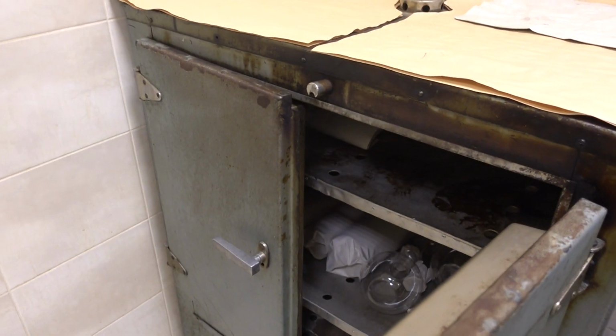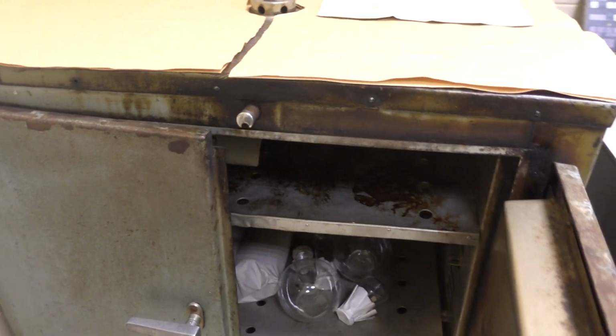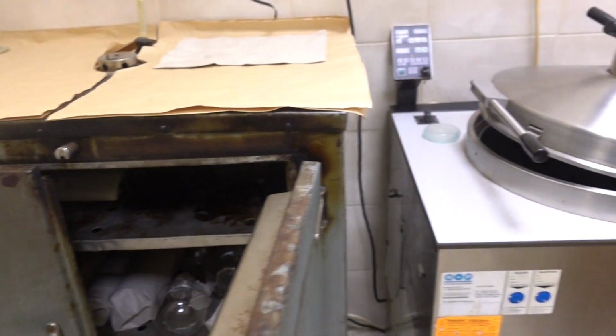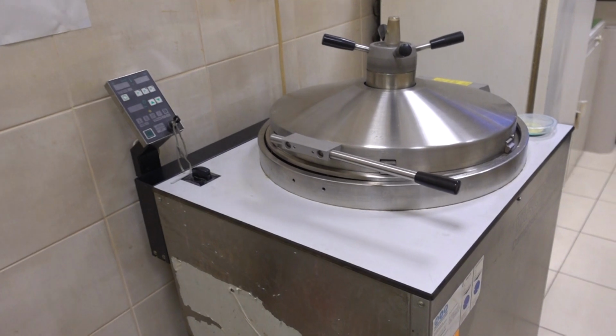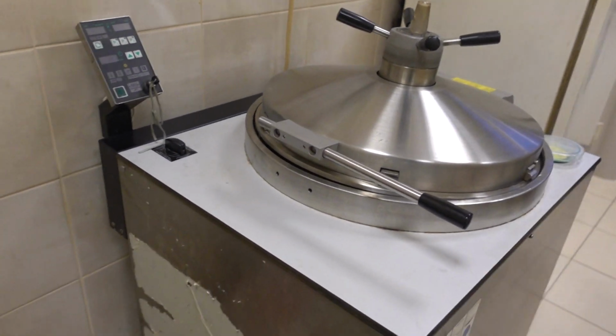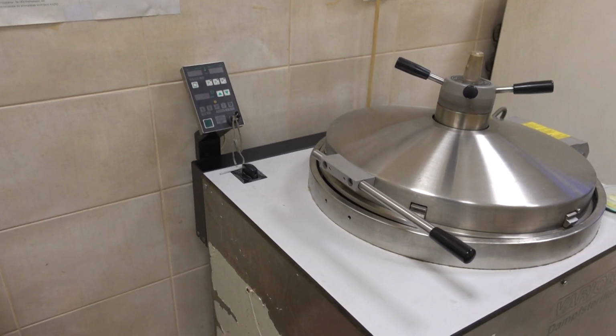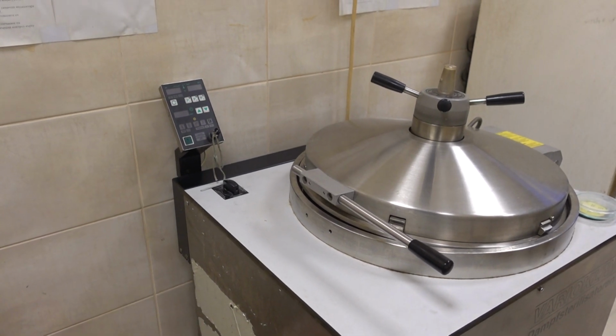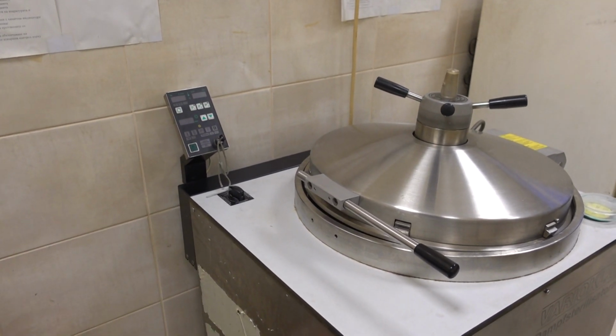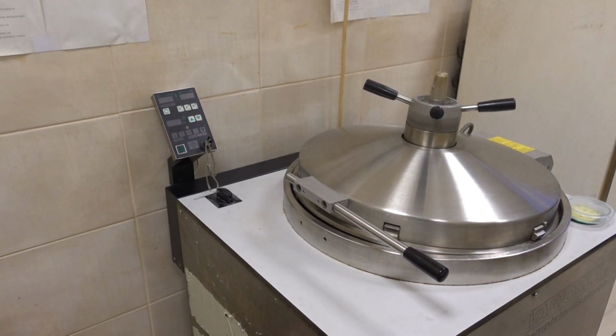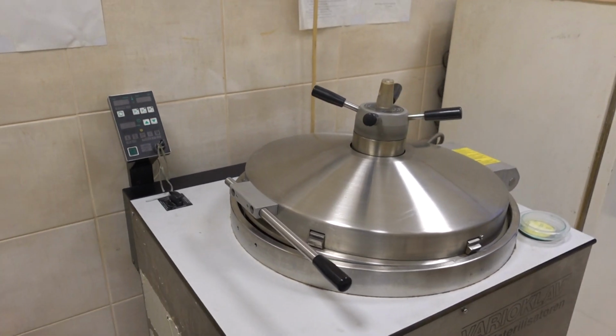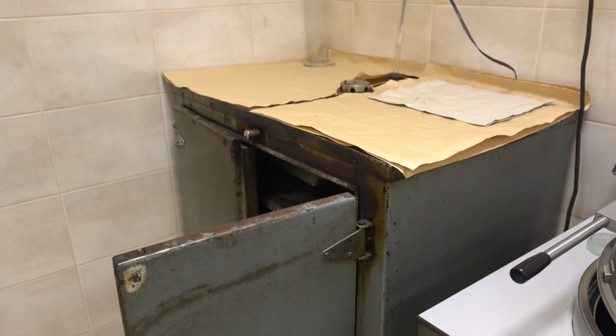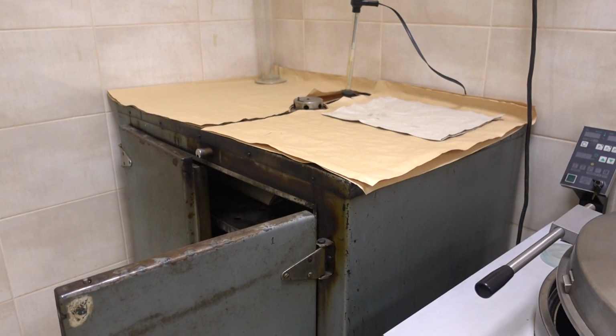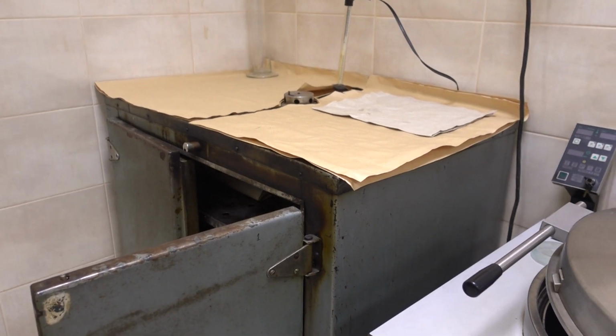This looks like a paradox. Take a look again. The hot air oven needs more than 1 hour for temperature at least 160 degrees, while the steam under pressure autoclaving needs lower temperature and much less time. The answer to this paradox is steam and water-containing environment. Hot air is an insulator, so it takes much more time for the spores to uptake the heat.